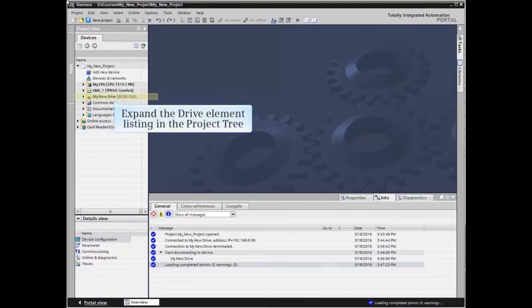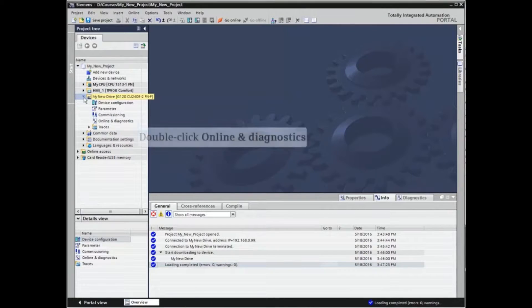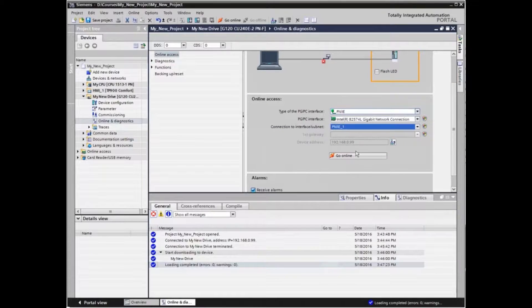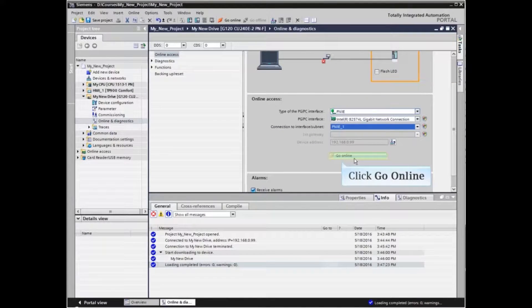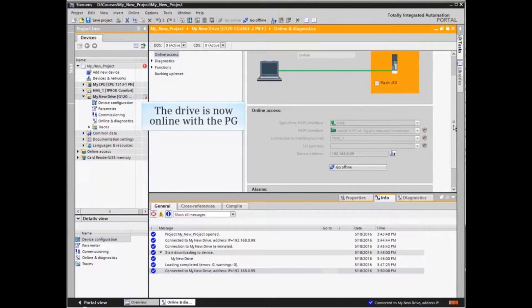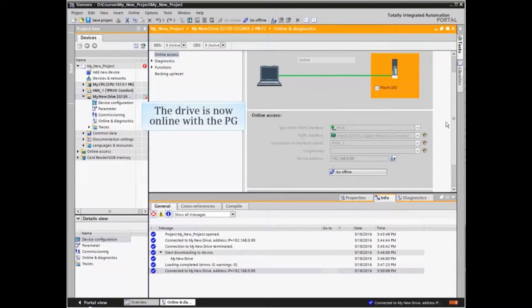In the project view of the TIA Portal project, expand the drive element listing in the project tree. Under the drive element, double-click Online and Diagnostics and click the Go Online button. The drive is now online with the PG.